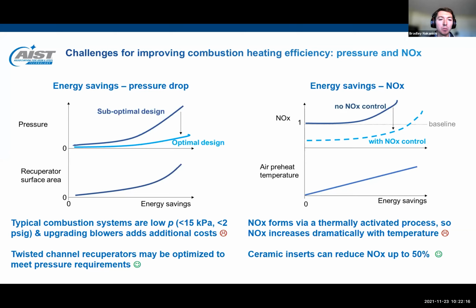Fortunately, twisted channel recuperators may be optimized using computational modeling to minimize pressure drop and avoid blower upgrades while providing energy savings. Looking on the right, reducing energy use by recuperation increases the preheated combustion air temperature as more heat is transferred from the exhaust to the combustion air. Because NOx is a thermally activated process, you may find significant increases in NOx at higher flame temperatures while targeting additional energy savings. Fortunately, this may be avoided by utilizing ceramic inserts to reduce NOx by up to 50%.